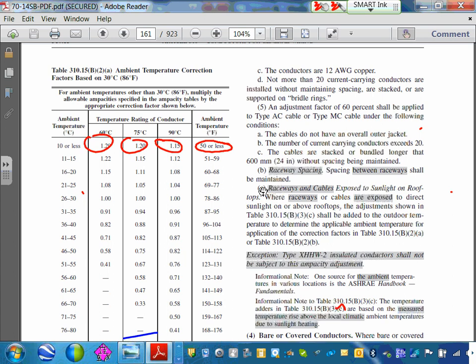I don't know if any engineer can use that. Typically, we don't add more ampacity. So the cutoff, can you see the cutoff right here? This is your cutoff. So that's when you start losing. If you stay within this temperature, like 26 to 30 degrees or 78 to 86, you will not lose or gain, exactly the same. If you go colder, the conductor can carry more amps. You know that, but don't size based on this. Absolutely, leave it at 100%. Why? Because it's safer, still safer.